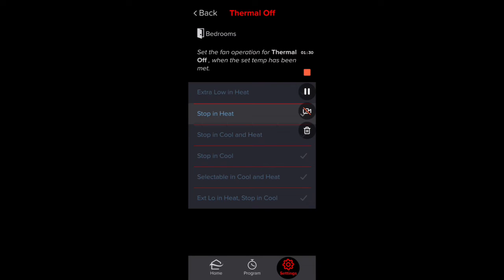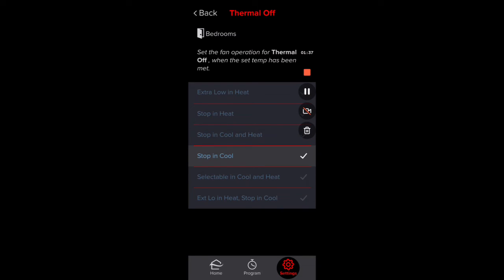Of course you can stop it in heat mode, stop it in cool and heat mode, or stop it just in cool mode. You can also stop it in cool mode and have Extra Low in Heat. Or if you want the fan circulating, you put Selectable in Cool and Heat — which means whatever fan speed you set on your remote control or thermostat, that'll be the fan speed. So if you have it on high and the system is satisfied, it will continue to blow on high.